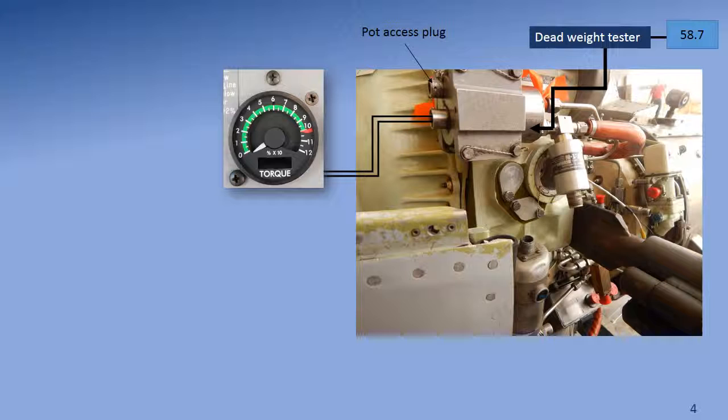Note the gauge is connected to the transducer. The plug on the transducer can be removed and inside are two pots, R and Z. R stands for range, Z stands for zero.